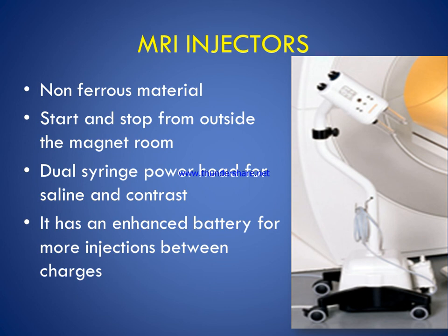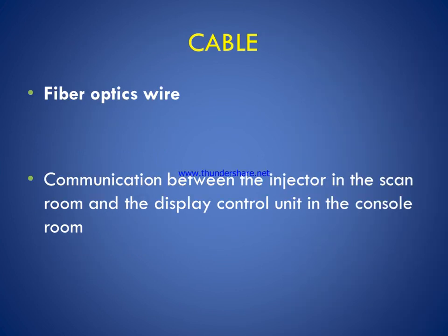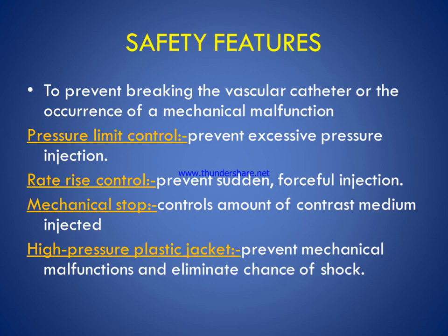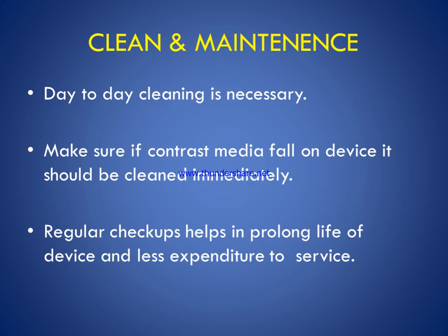For the MRI injector, the device is made of non-ferrous material and can be started or stopped from outside the magnet room. It has a dual syringe power head for saline and contrast, and an enhanced battery for use between charges. The cable used in the MRI pressure injector is made of fiber optic wire, providing communication between the injector in the scan room and the display control in the console room.